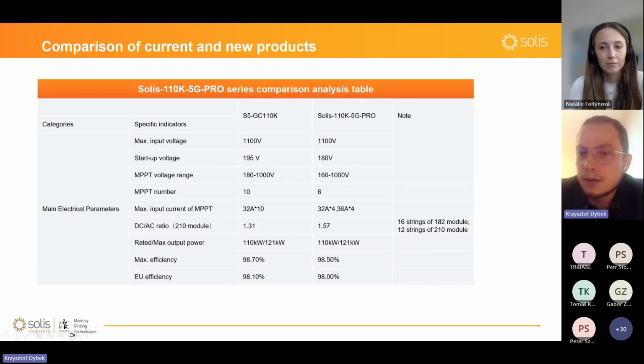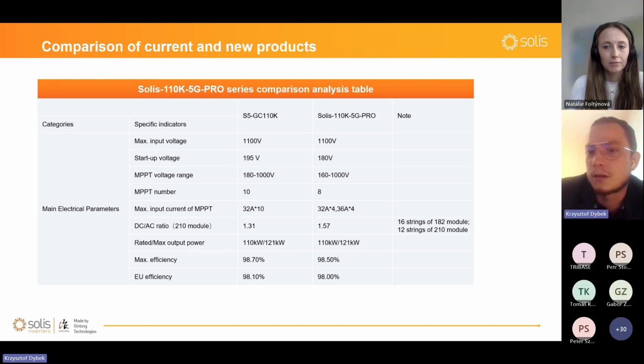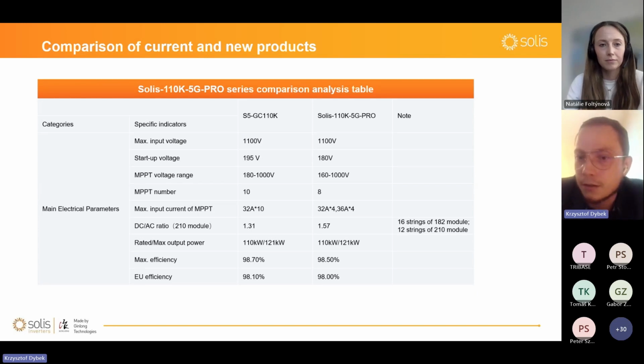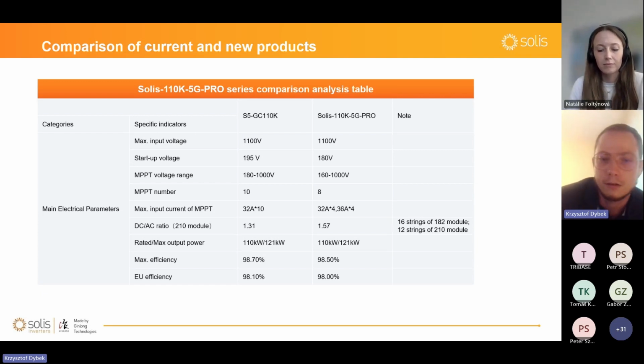What else can we see? The biggest difference between the normal and the Pro version is that the startup voltage is a little bit lower, and there is a bigger DC-AC ratio and bigger current allowed per MPPT. Why are there fewer MPPTs than in the normal version? The answer is simple. PV modules are changing in the direction of high power and high current. And the mainstream of the market uses 182 millimeter modules and 210 millimeter modules, which have increased current requirements for each string.